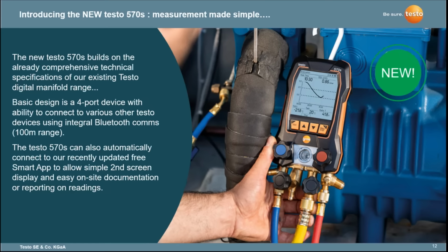So the 570s really builds on the background of our 55X series of manifolds, as we call them. These were released initially about 2 years ago, and it brought to the market a complete update and refresh for the testo digital manifolds. So the 570s is a 4-port device. So it has your low pressure port, your high pressure port. There's also a port for adding refrigerant to charge into the system. And there's also a larger connection if you want to evacuate or vacuum the system through the manifold.